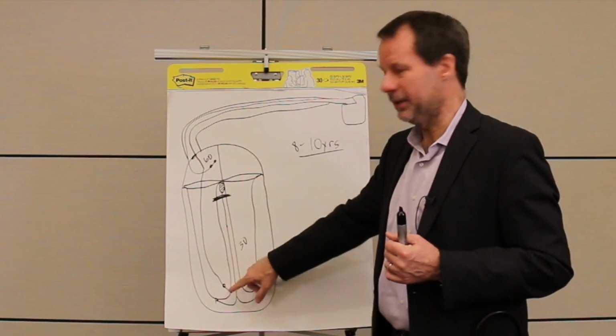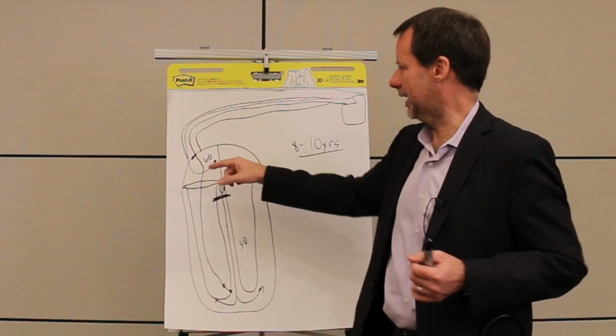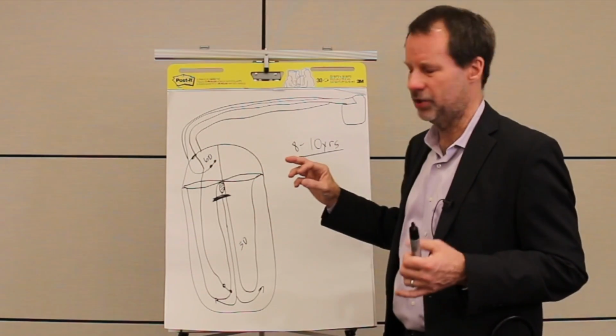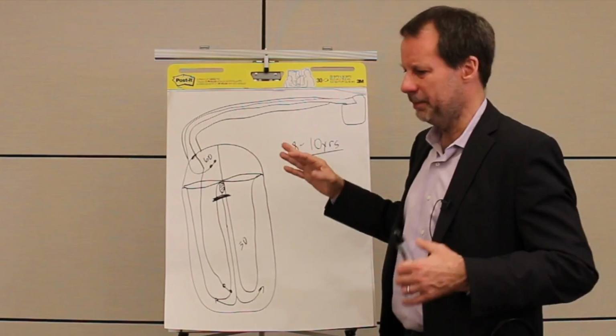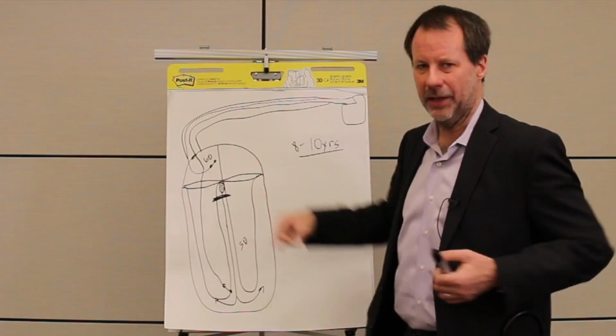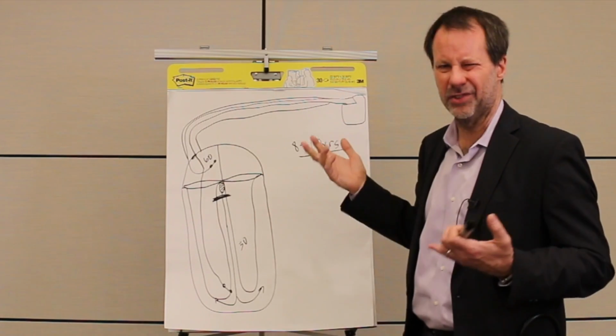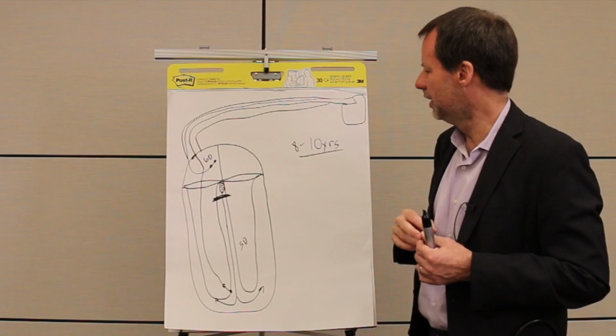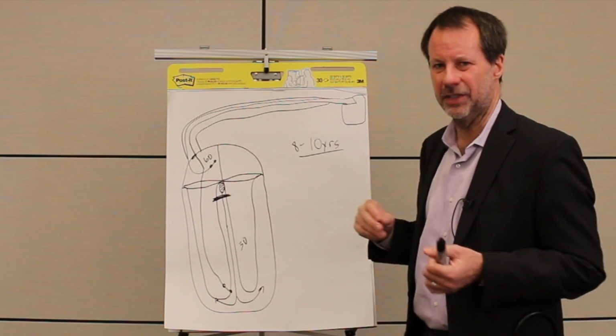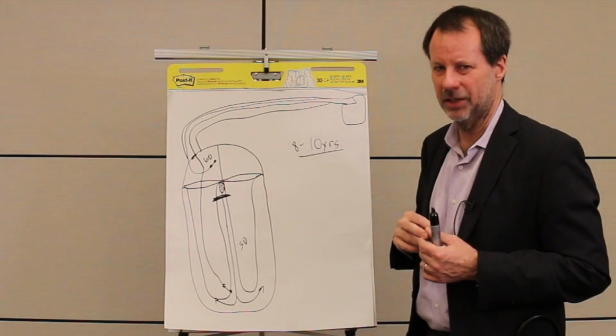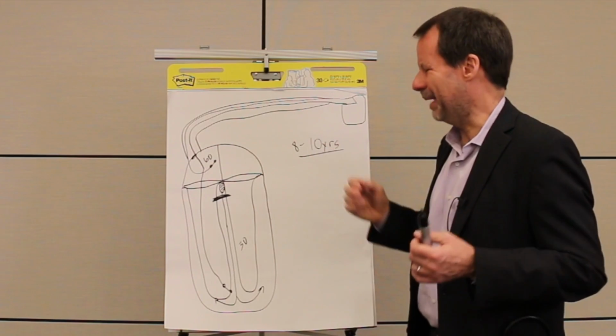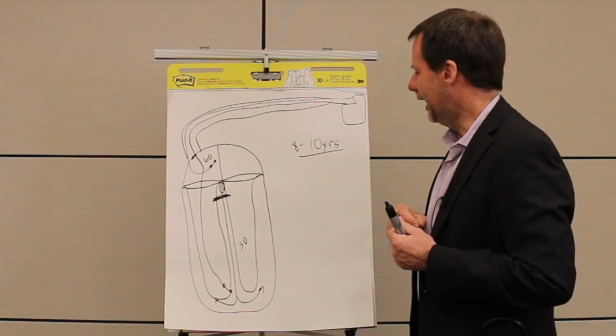Wires can fall out of position. As I said before, there's a little tiny screw on the end of the wire that holds it in place. That doesn't happen often, but if it does, we have to go back and replace them. Generally, if they stay in for the first 24 hours or so, they're going to stay in for the long haul, so dislodgement is something we'll pick up in the hospital on the initial admission. It happens maybe 1 in 20 or less.